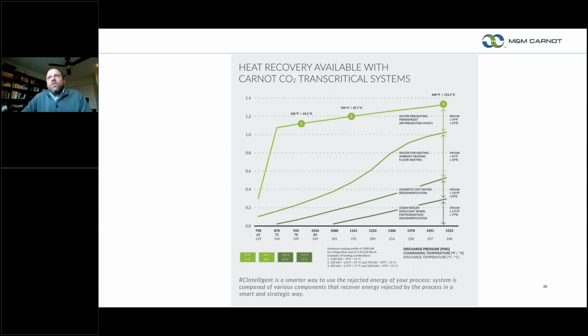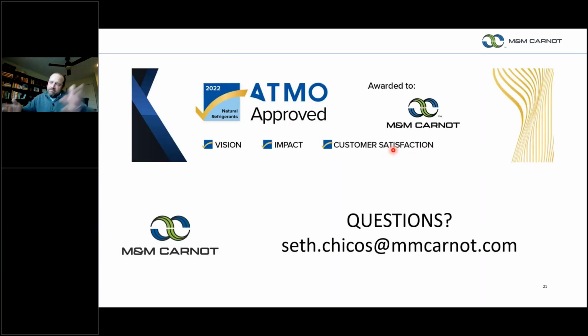In the data center business, we want to come out with general building blocks. Now, I'm not saying we won't entertain questions about custom chillers that can do heat recovery, but our goal is to have certain building blocks that can be applied in data centers and used how they want. That was where the 80-ton chiller that I started with comes in. In a data center application, I think it's perfect, creating 131 degree water. If you need a different temperature, we can take that offline and talk a little bit more about that. But that was the introduction of what I wanted to talk to you about. We're excited. We are an ATMO approved manufacturer of refrigeration equipment. That was something we got a couple of months ago.